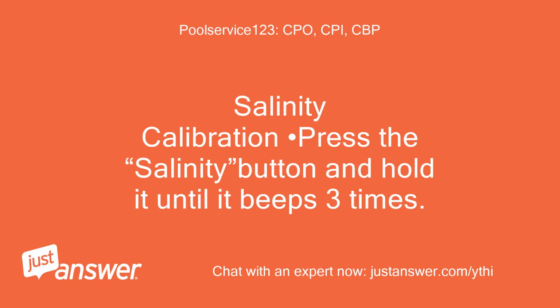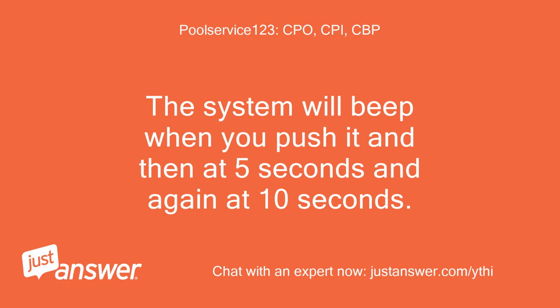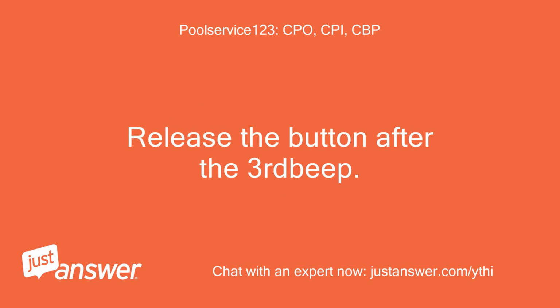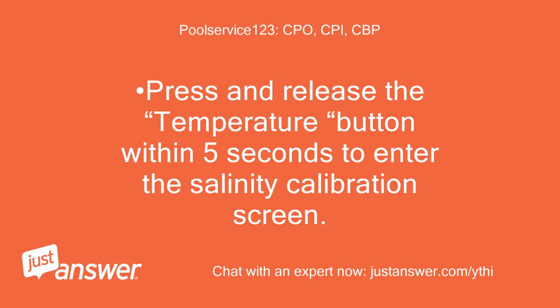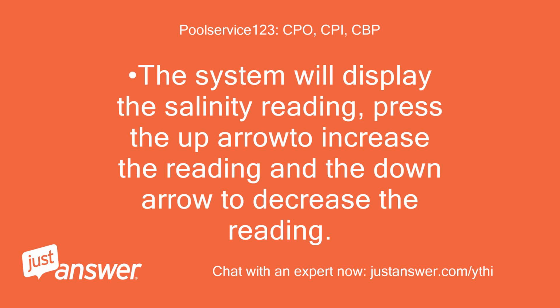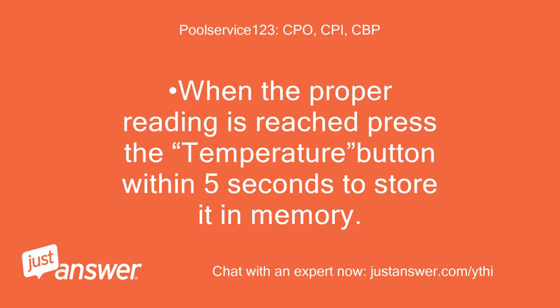Salinity calibration. Press the salinity button and hold it until it beeps 3 times. The system will beep when you push it, and then at 5 seconds and again at 10 seconds. Release the button after the third beep. Press and release the temperature button within 5 seconds to enter the salinity calibration screen. The system will display the salinity reading. Press the up arrow to increase the reading and the down arrow to decrease the reading. When the proper reading is reached, press the temperature button within 5 seconds to store it in memory.